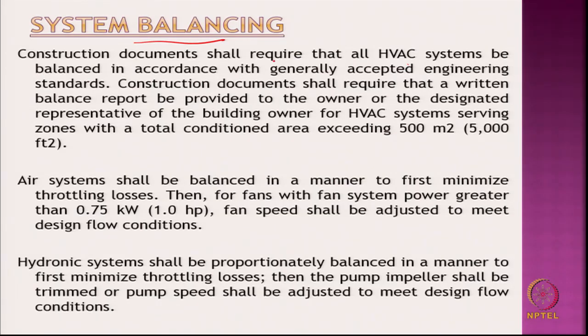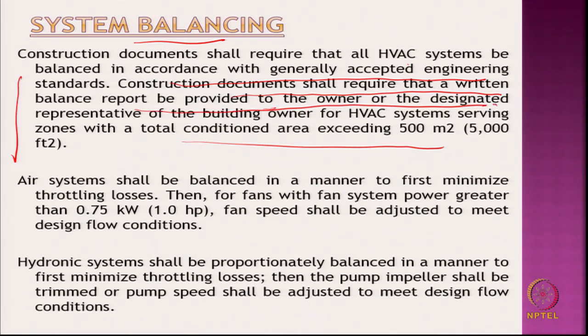Then there is a clause related to system balancing. The system should be balanced according to generally accepted engineering standards. That means for the quality of the HVAC system there are some guidelines as well. Construction documents shall require that a written balance report be provided to the owner or the designated representative or building owner, etc., for HVAC systems serving zones with a total conditioned area exceeding 500 square meters. So certain documents are to be prepared, and all losses, etc. This is also to be prepared.